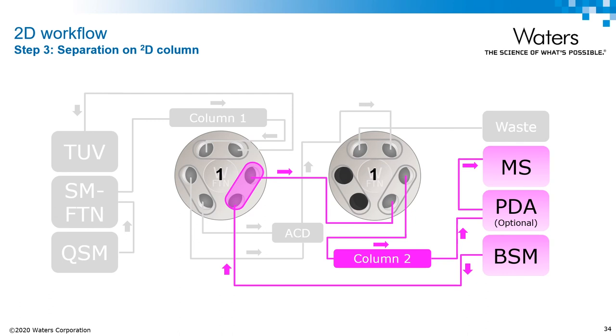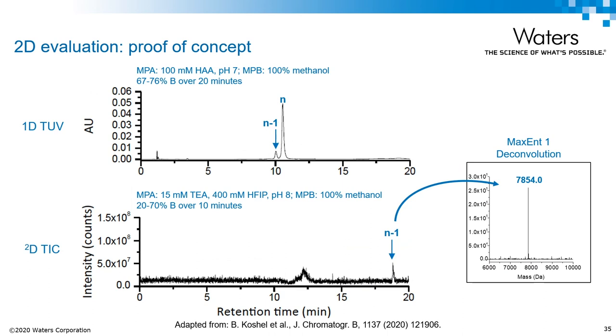The second dimension pump now drives the separation in the second dimension. A proof-of-concept experiment was used to evaluate the 2D system. The N-1 impurity was spiked into the full-length product at approximately 10%, as determined by integrating the optical trace in the top figure. When the N-1 impurity started to elute, it was transferred to the second dimension. The corresponding second dimension TIC was used to confirm the mass of the N-1 peak from the deconvoluted data. The broad peak at about 12.5 minutes in the TIC is attributed to mobile phase from the first dimension passing through the second dimension column during the heart cut when the flow paths are combined.